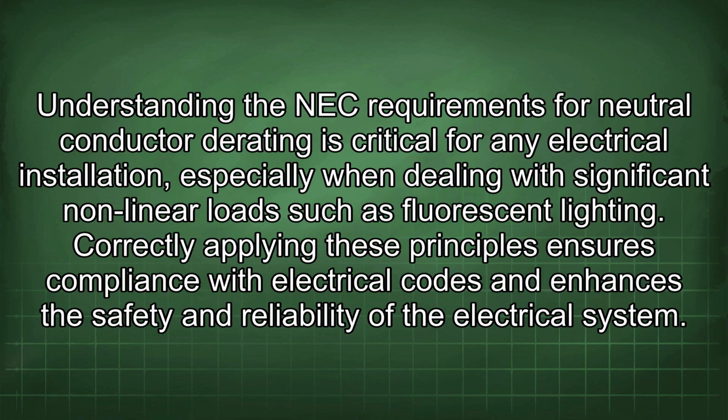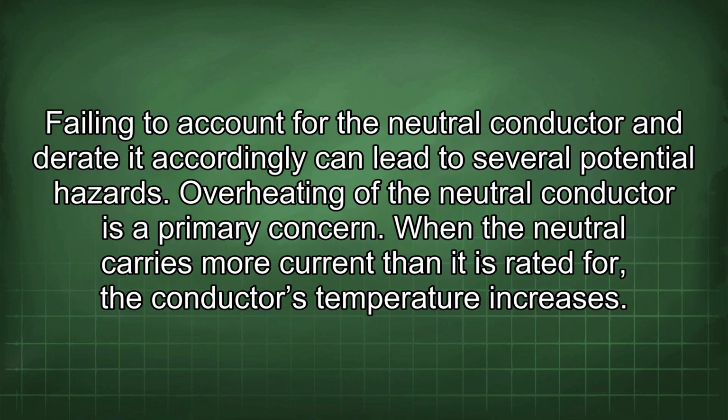Understanding the NEC requirements for neutral conductor derating is critical for any electrical installation, especially when dealing with significant nonlinear loads such as fluorescent lighting. Correctly applying these principles ensures compliance with electrical codes and enhances the safety and reliability of the electrical system. Failing to account for the neutral conductor and derate it accordingly can lead to several potential hazards.